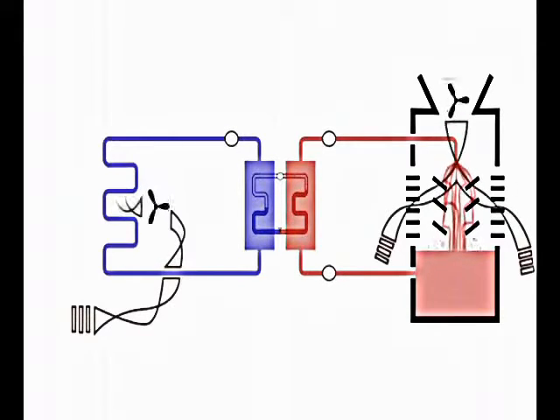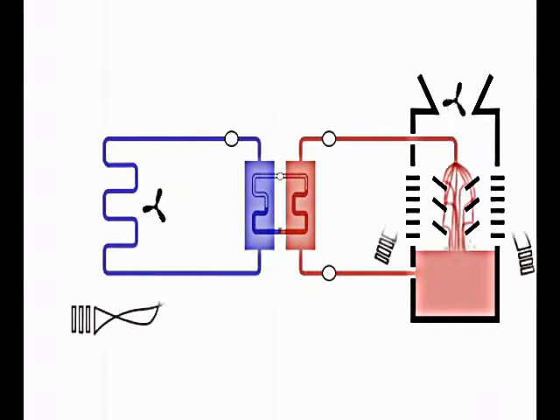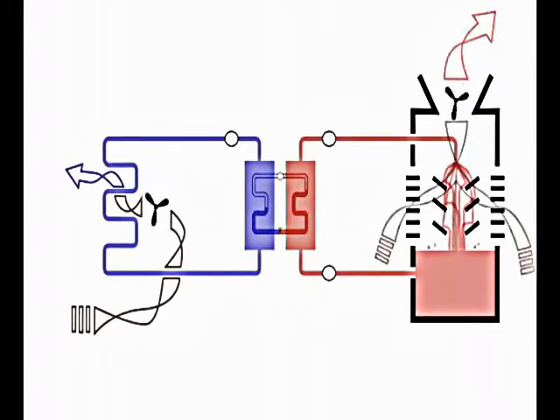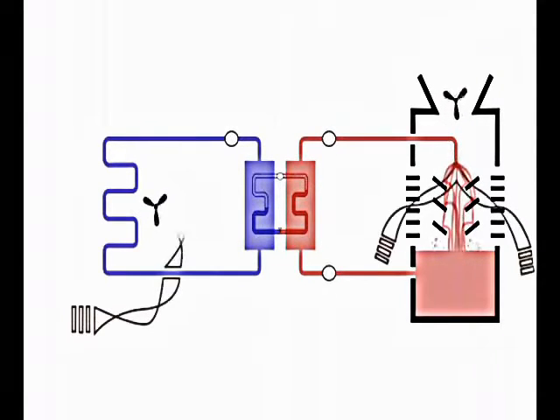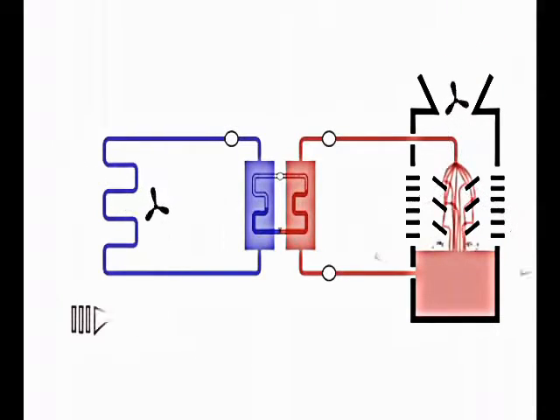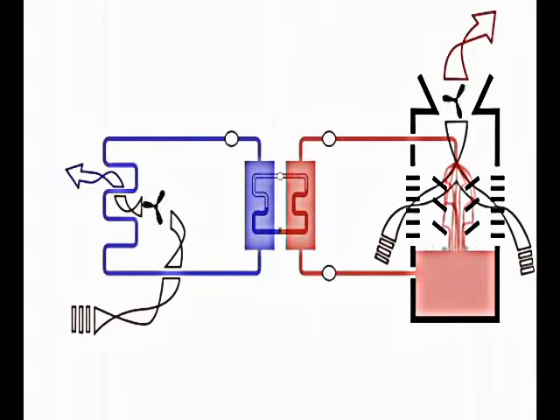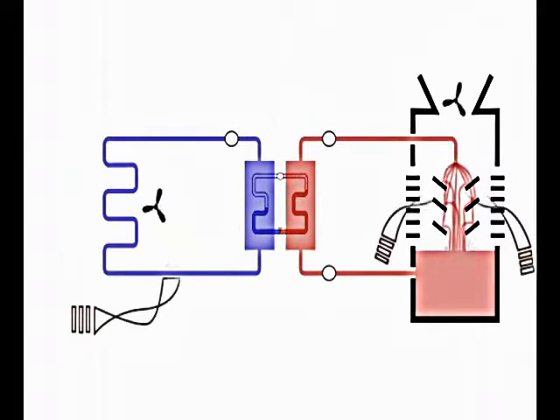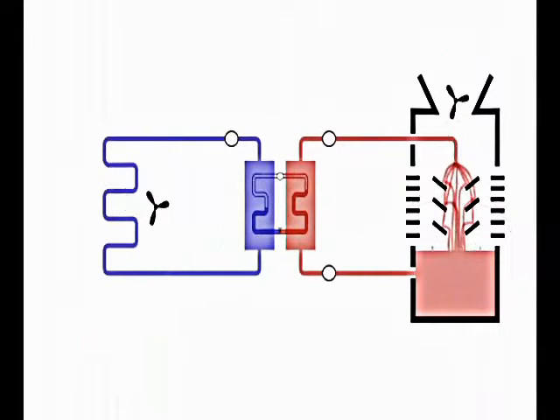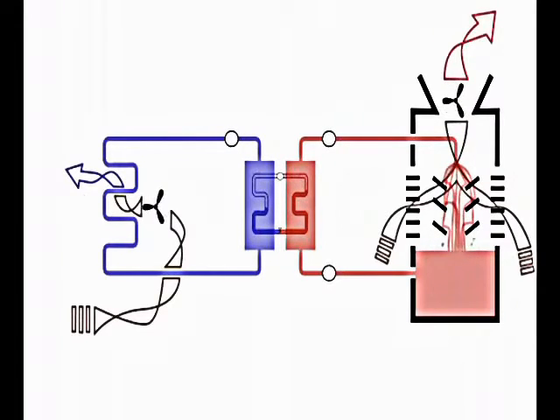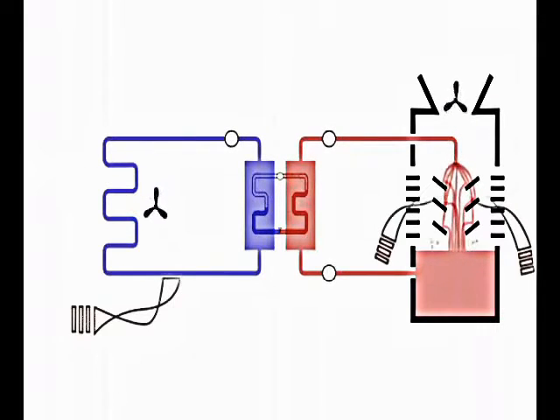This distribution network using water is complicated, but not exceptionally complex. Let's review. Water is cooled by the evaporator and distributed to the air handling units to cool room air. A separate loop of water cools the condenser and carries its heat to the outside air via a cooling tower. You've seen cooling towers on roofs and adjacent to buildings or as part of central chiller plants. The machine that does the compression refrigeration loop in this layout is termed a chiller.